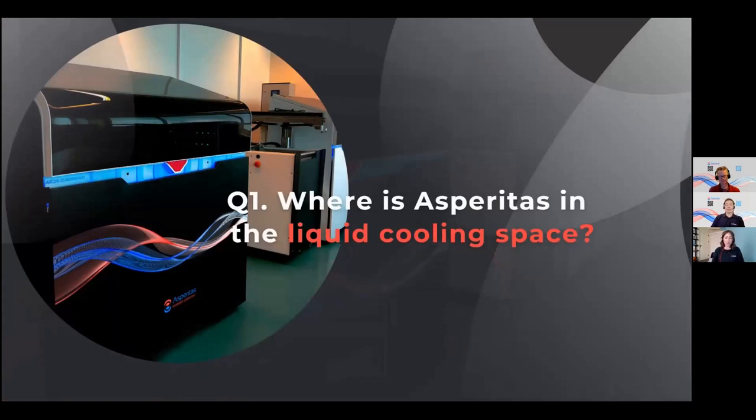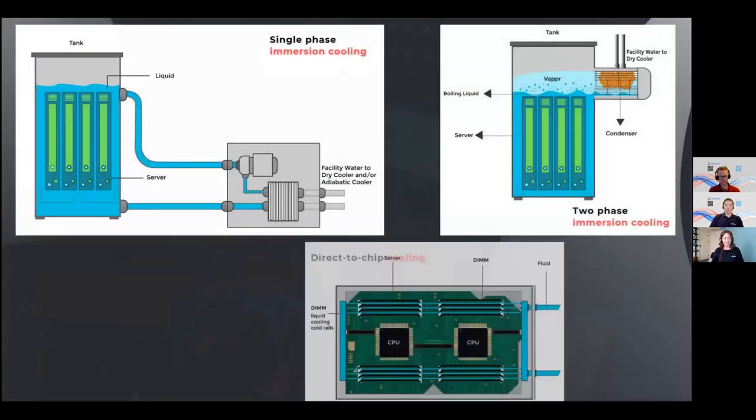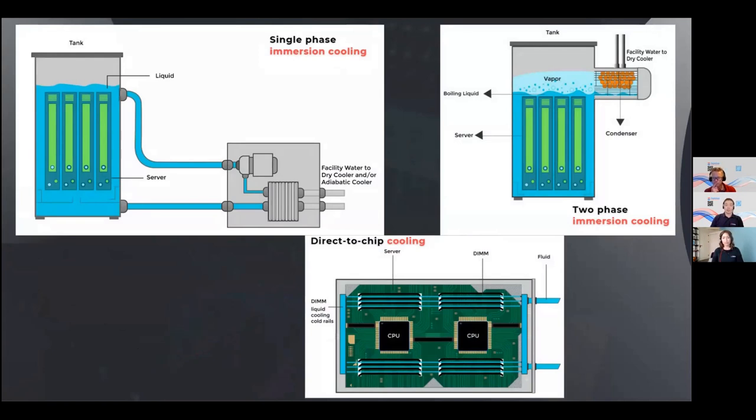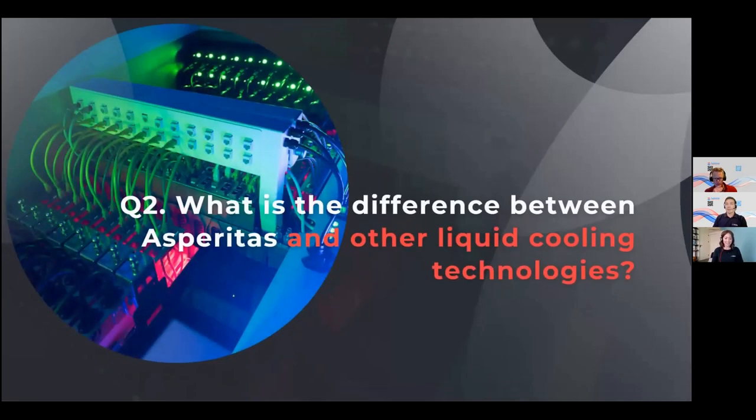There is a lot of talk about liquid cooling for data centers. Could you quickly introduce Asperitas and where in the liquid cooling space we are? Within liquid cooling there's a variety of solution categories. You have direct water cooling, which you see here on the bottom where we bring liquid to the components directly attached, and then there's immersion cooling in two main categories: single phase immersion cooling and dual phase immersion cooling. Asperitas is offering a solution in the single phase immersion cooling.